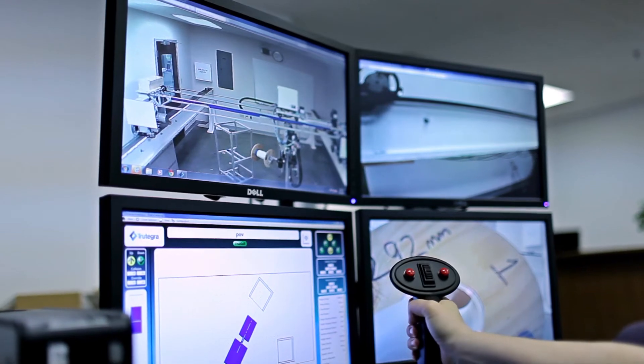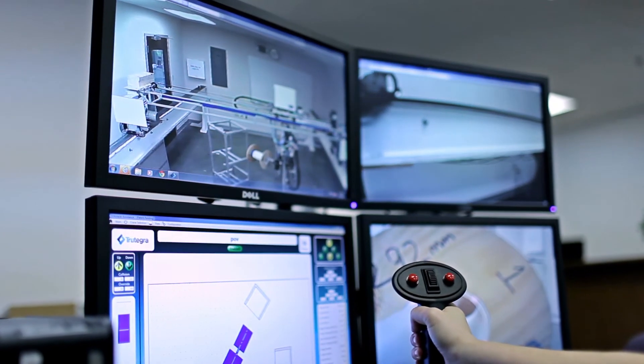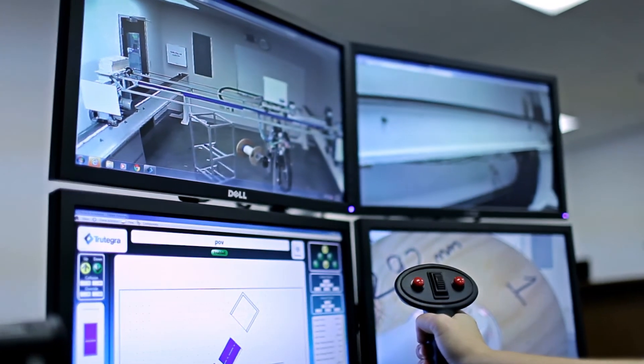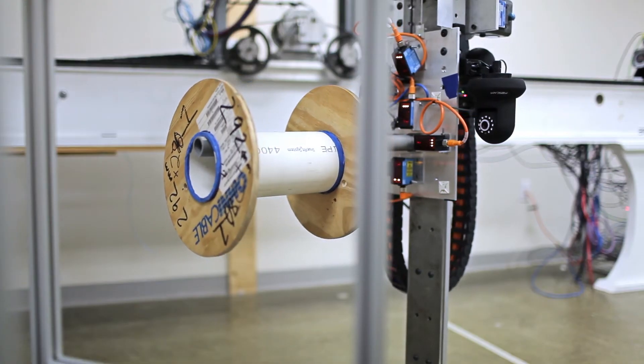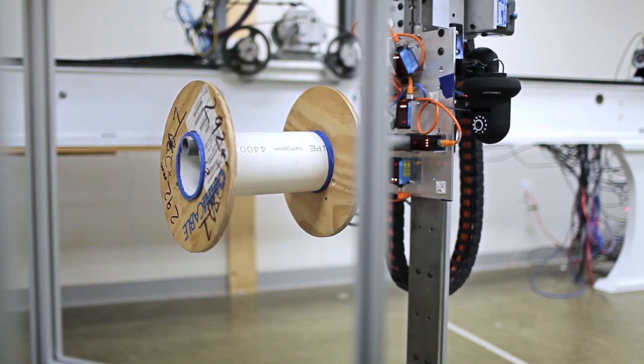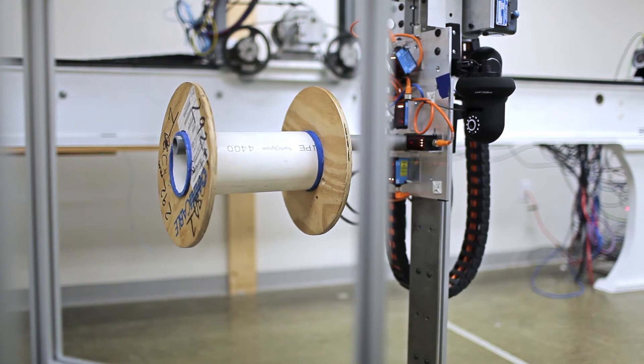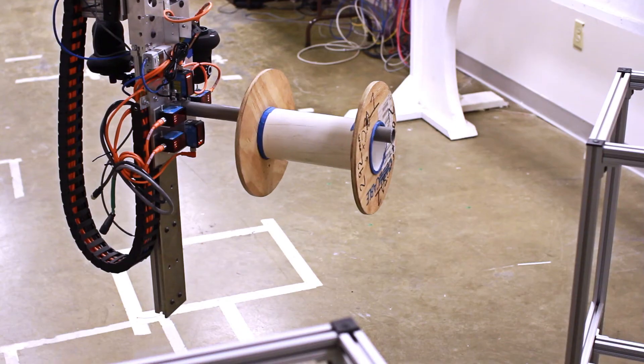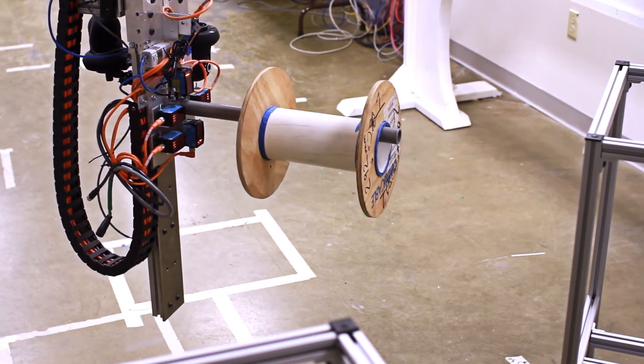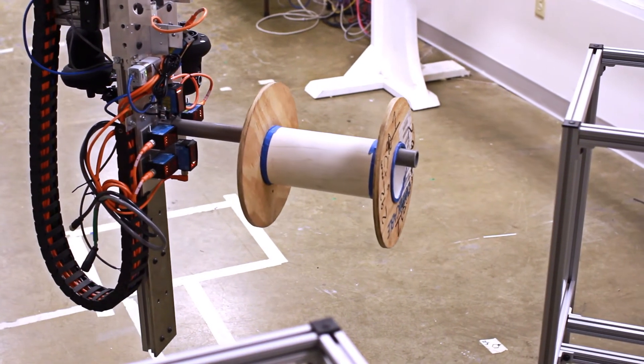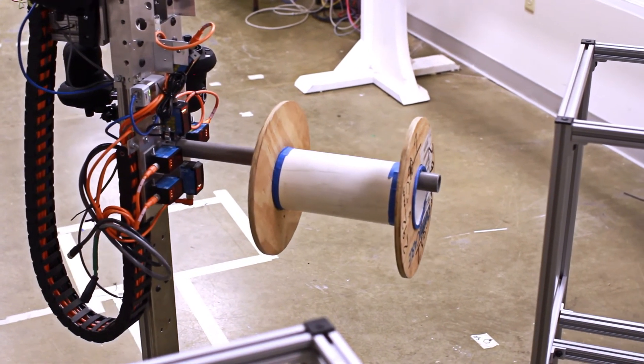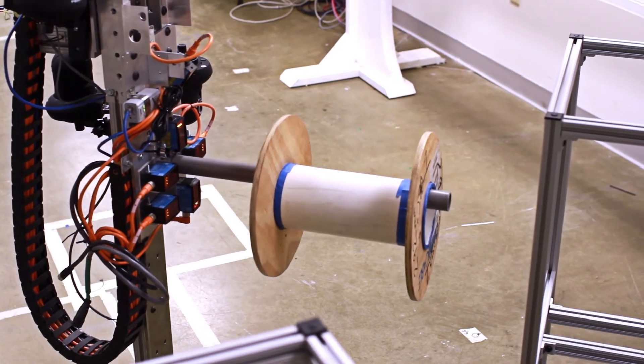Throughout all moves, both manual and automatic, TrueTegra's obstacle avoidance intelligent software monitors all crane motions and intervenes to slow the crane if the commanded motion threatens to contact known structures.